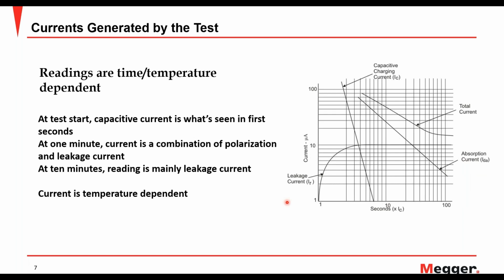This is the graph that I was talking about. Usually within the first few seconds, this is your capacitive charging current that dies down. It is just used to charge the object under test. Second one is your absorption current that lasts a little while longer, about a minute or so. And then you have your leakage current that increases with time and stabilizes after about 10 minutes. It usually stabilizes much faster, but at 10 minutes, what you see is definitely everything leakage current.